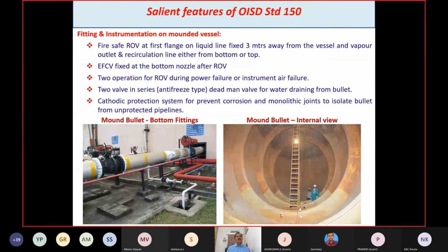Excess flow check valve means, this is a spring loaded check valve. Actually, the seat of the valve will be held open by the spring. So whenever the fluid flow exceeds the predetermined limit, or due to line puncture or any failure of the downstream side, immediately the valve will close automatically and instantly. So that is called excess flow check valve.